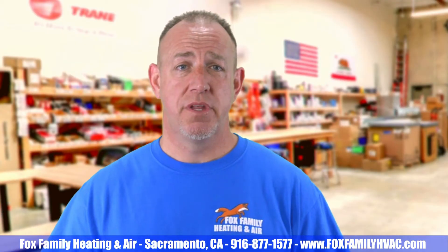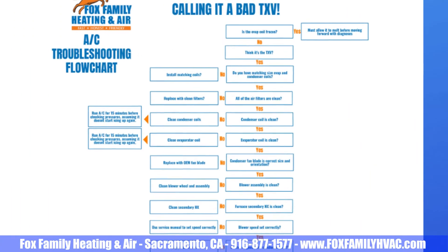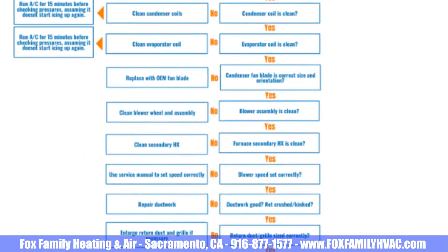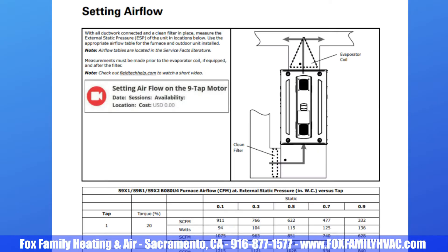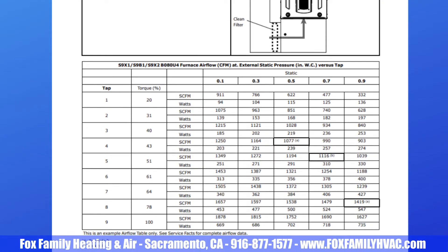Check these basics first. Before you condemn that TXV, make sure that you've checked the fundamentals. Everything relies on a balance of refrigerant and airflow across these coils, and it starts with the right size equipment. Assuming you have matching sized evaporator coil and condenser coils, make sure that you have 300 to 400 CFMs of air going across the evaporator coil. Are the air filters clean, and are there more than one? Are the condenser coils clean? Is the evaporator coil clean? Is the blower assembly clean? If it's a condensing furnace, is the secondary heat exchanger clean? Has the condenser fan blade been changed since the original install — is it still the right size, removing heat efficiently? Check the airflow chart inside the book; it'll give you details about where the dip switches or speed taps need to be to achieve proper CFMs of airflow for that particular setup.